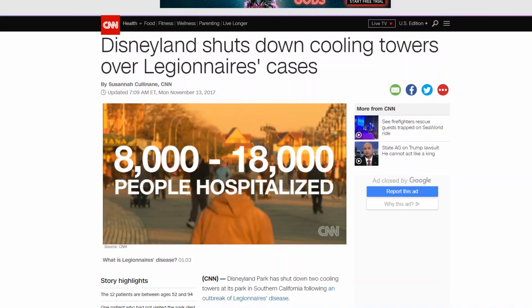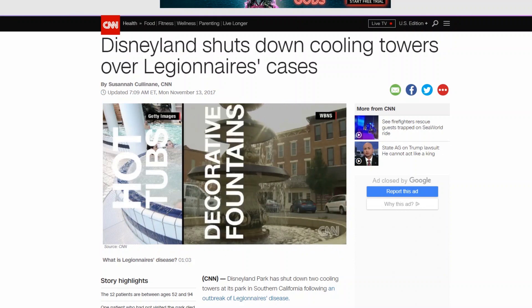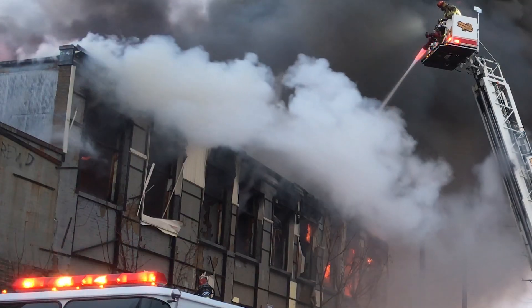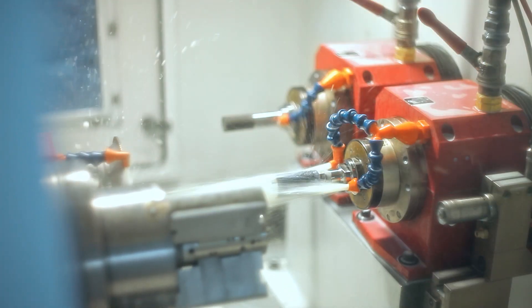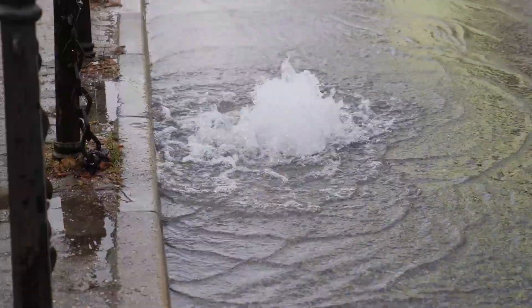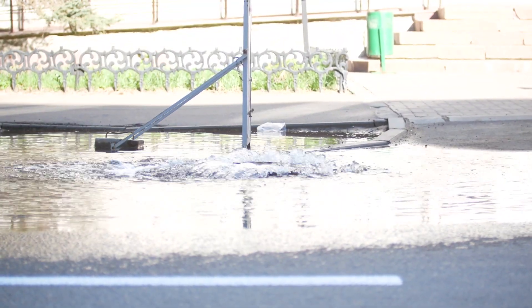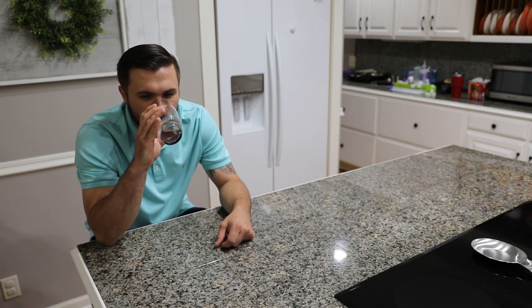If no protections existed, water that is cycled through cooling systems in large buildings becomes a breeding ground for bacteria as the water heats up. Water in fire suppression systems often sits stagnant for years and even decades if there is no fire, making the water stale and undrinkable. Chemicals used in manufacturing processes could make their way into your drinking water if the pressure gets higher within the factory than the pressure on our system. Plus, since water likes to take the path of least resistance, a main break caused by materials failure or construction damage could cause this undesirable and often undrinkable water to be siphoned into our distribution system and possibly into your glass of ice-cold water.